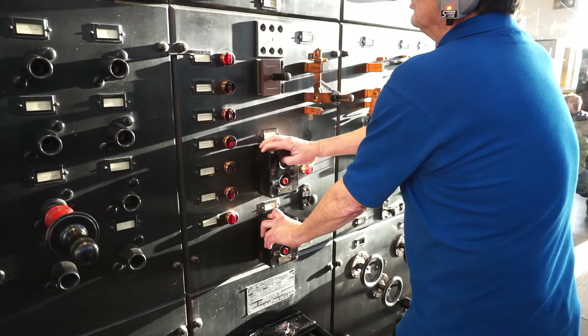I think it's time to close the rectifiers. And then Anders will go over to the other side of the panel, and he will close a switch with 500 volt DC. And then he saturates the transductors, so they will give full voltage 2,300 volt to the main motor, and you can hear it revving up. At 700 revolutions per minute on the main motor, he will close the next switch with 250 volt DC. And by that he is magnetizing the high frequency generator, and it starts to generate a carrier wave.